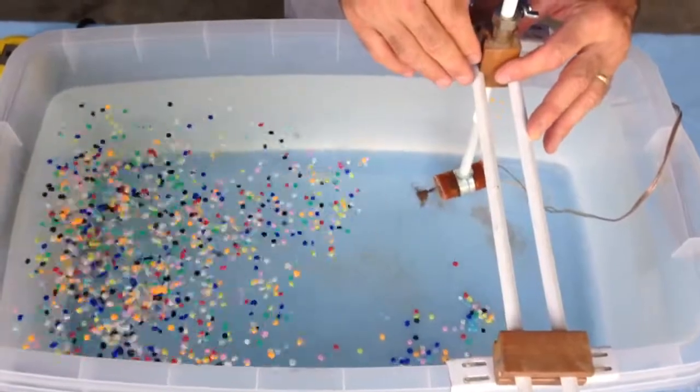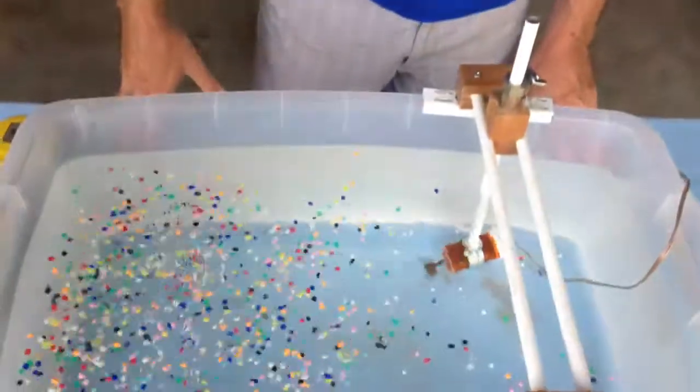Looks good. This position that you're seeing here, a quarter of the way from the end, just off the wall here, and anywhere from 15 to 30 degrees, actually closer to 30, is what our standard recommended position is for basins within the ratio of 2.5 to 1 for one mixer. There are exceptions. It can be a little bit more than 2.5 to 1, but you need to increase the mixing power. But what you're seeing here is our recommended positioning, and you can see we've got a good roll coming back. Hardly anything settled on the bottom, stabilized pattern now.